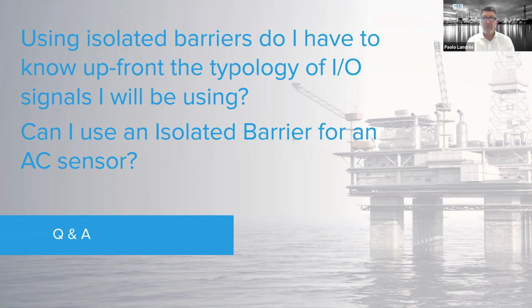The question is about IS barriers and IS sensors of different approval bodies. Yes, of course. The IS barrier is the concept, and the sensor is CSA approved. Well, it depends which standard they are approved to. Each laboratory or entity can certify according to different standards. For example, CSA can issue an IECEx certificate or can issue a CSA or a UL certificate. So it depends on the certification.